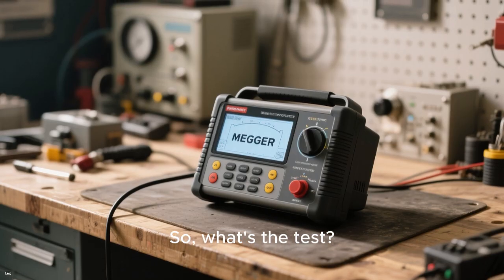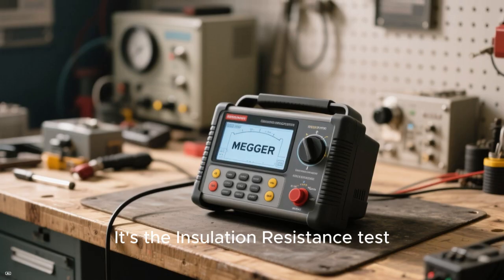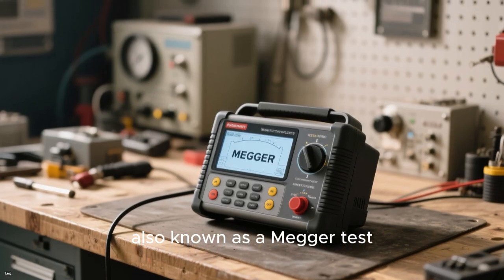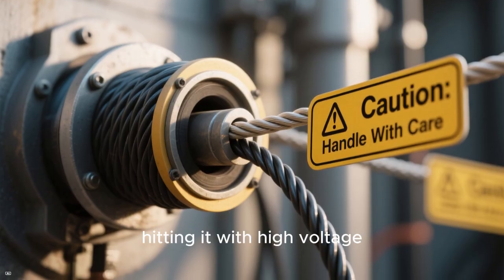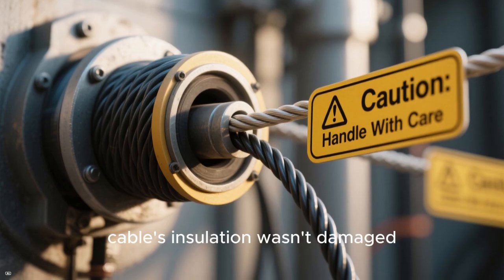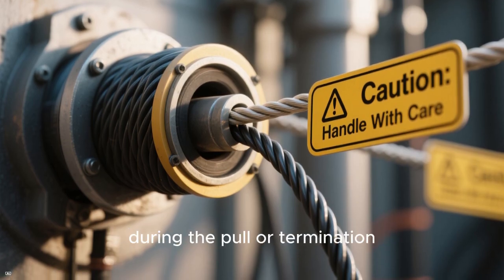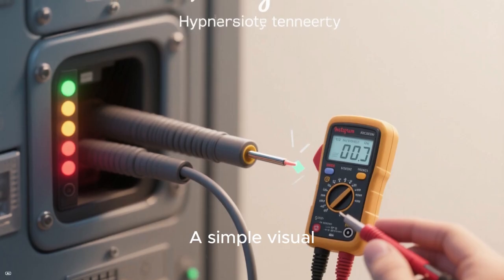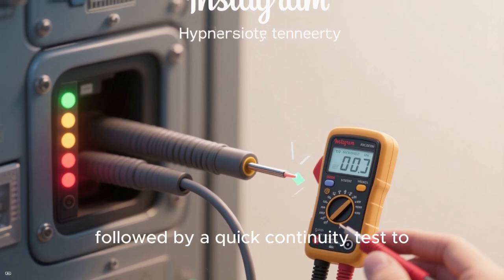So what's the test? It's the insulation resistance test, also known as a megger test. Before you even think about hitting it with high voltage, you need to confirm the cable's insulation wasn't damaged during the pull or termination. A simple visual check for kinks or jacket damage is your starting point, followed by a quick continuity test to make sure the conductors are intact.